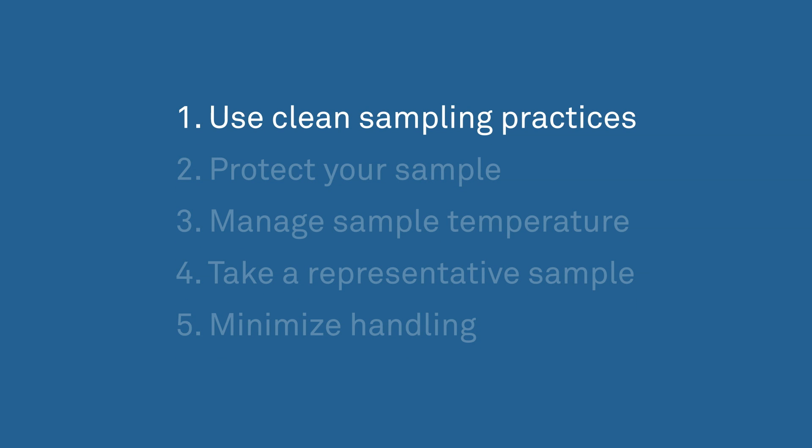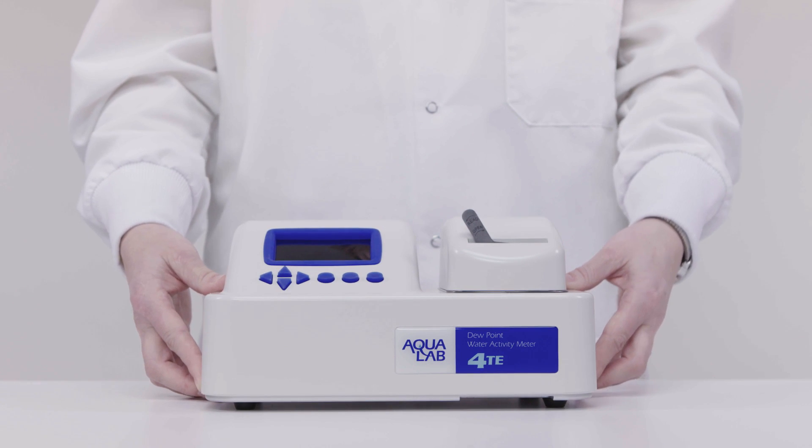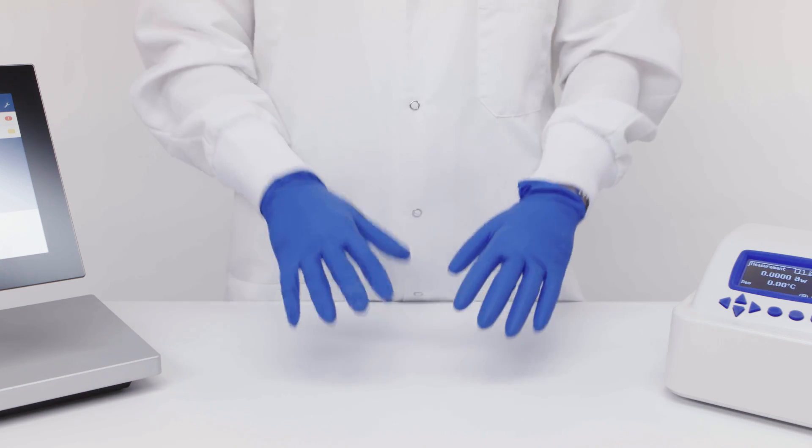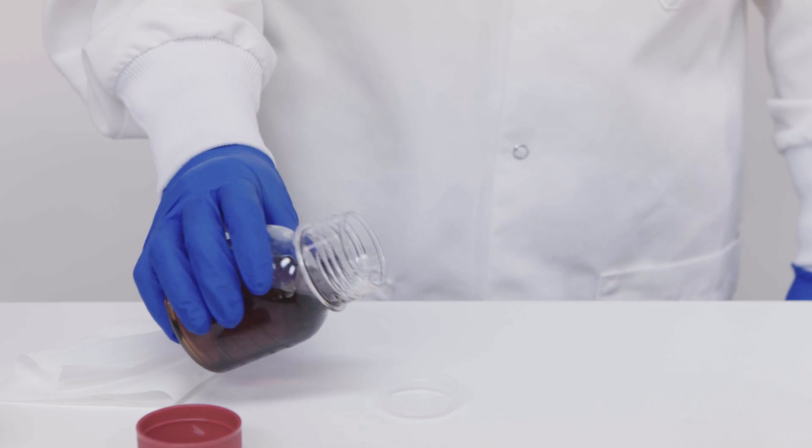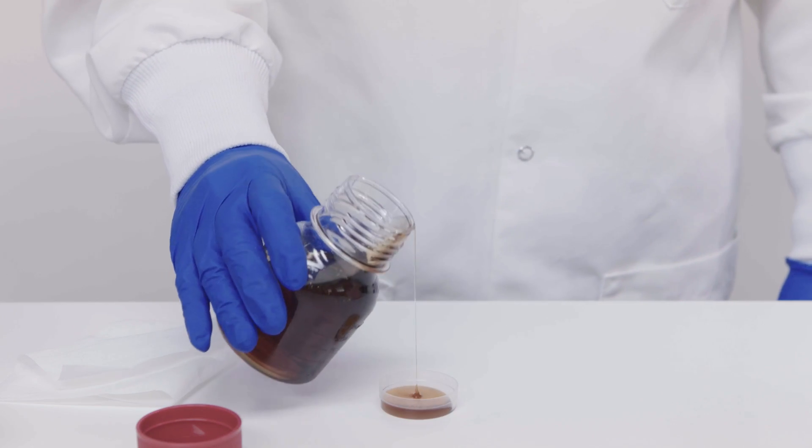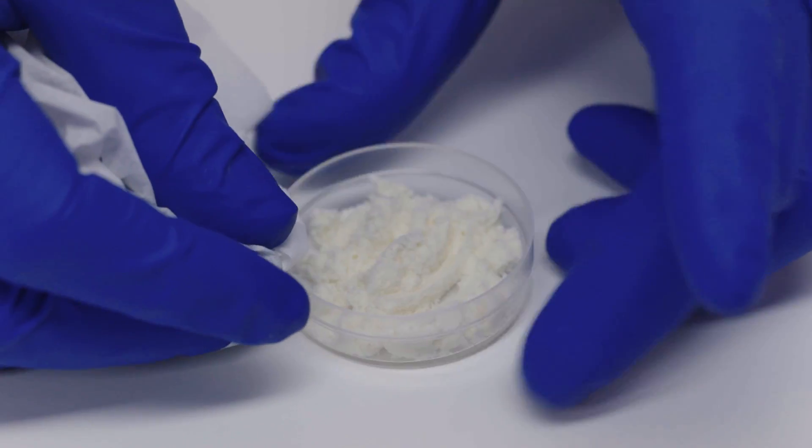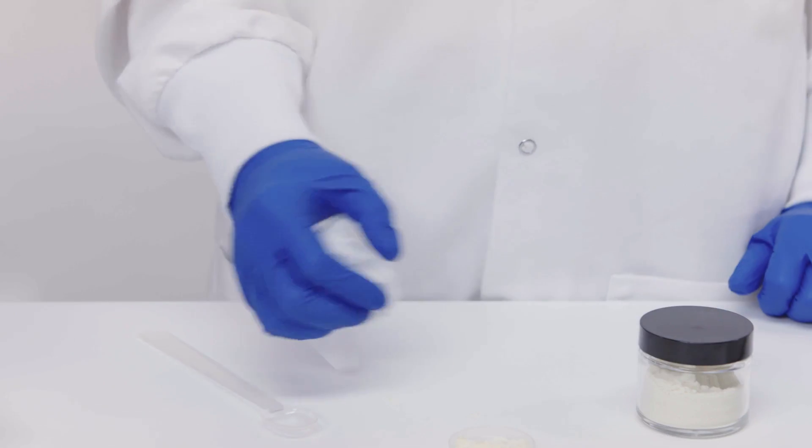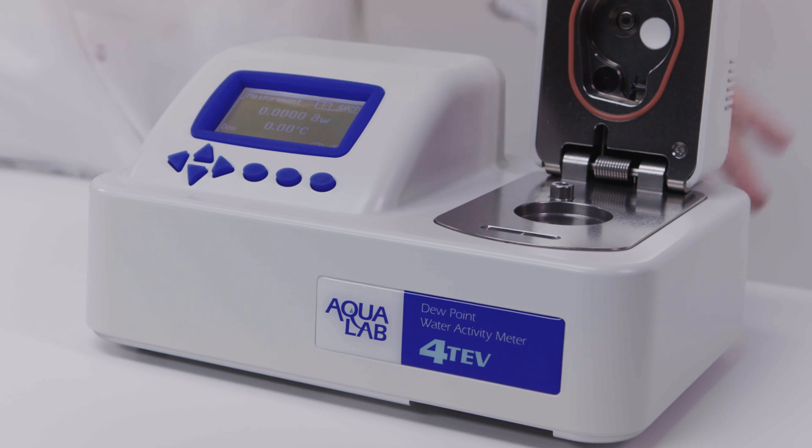One, use clean sampling practices. Place your instrument in a clean location. Make sure you have clean hands or wear lab gloves. Use a clean sample cup for each reading. Fill your sample cup no more than half full. Wipe the bottom, the edges, and the rim of your sample cup with a Kimwipe before putting it in the instrument so you don't contaminate the sample chamber. Even small amounts of water or contamination can significantly affect the reading.